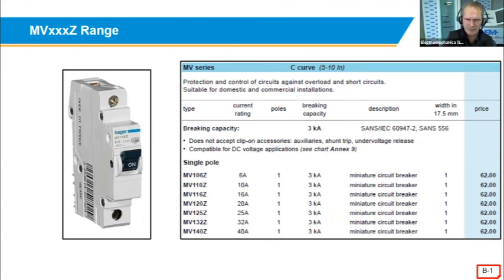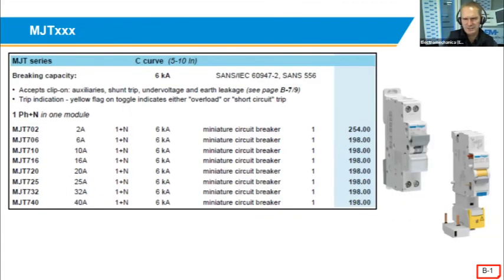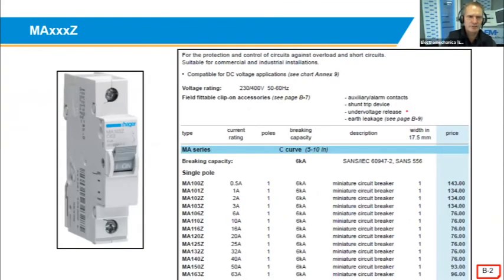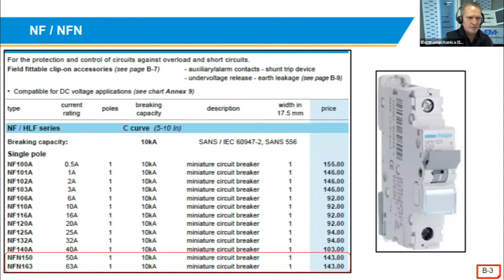explaining the MV product, that's 3 kA, the features of it, the MJT that can take an add-on earth leakage device. It's a 1 pole plus neutral product, so meaning the neutral is not protected, it's just an isolator. The 2-pole products in the other ranges are both protected, so it's overcurrent and short circuit protection on both these poles. The MA range, we've got the NF, so just be careful when you order here that up to 40 amp it's called the NF range, and for 50 and 63 amp it's called the NFN range.